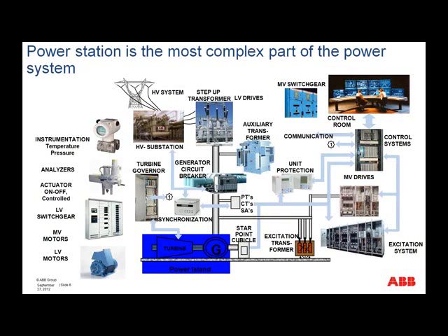Now, the power station, as this slide shows, is the most complex part of the power system. In this slide, we can see the generator with turbine. Here we have the generator, circuit breaker, step-up transformer out into the HV system. We also have here the auxiliary transformer, excitation transformer, and a host of other things.